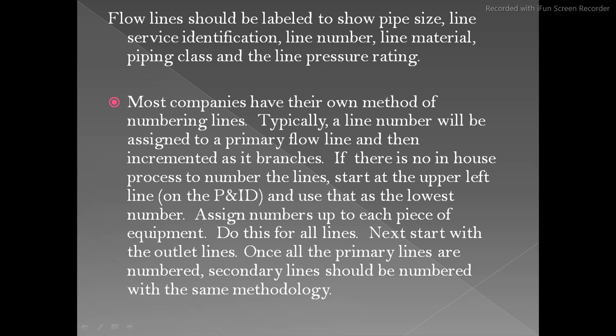If there is no in-house process to number the lines, start at the upper left line on the P&ID and use that as the lowest number. Assign numbers up to each piece of equipment — once they complete the process line numbering, they then start with the utility line numbers. Do this for all lines.